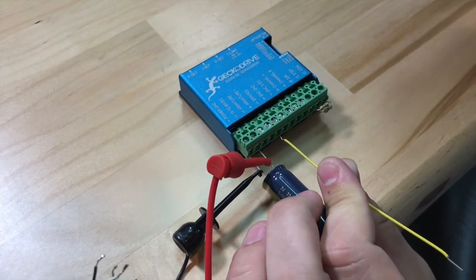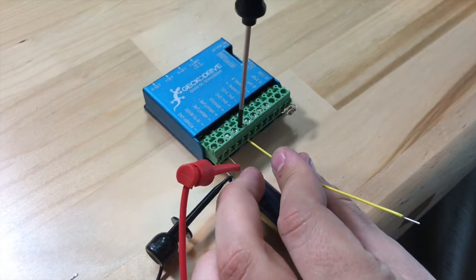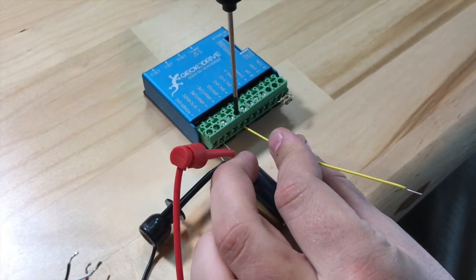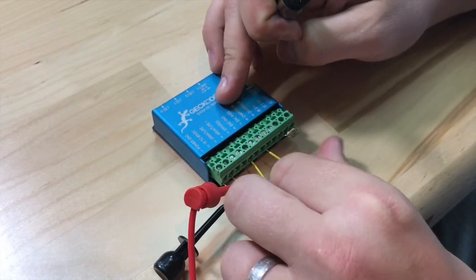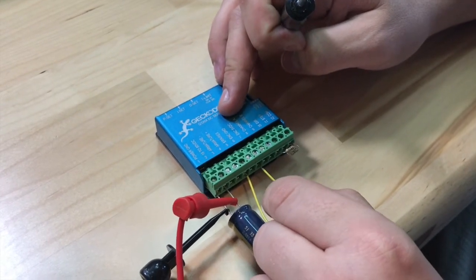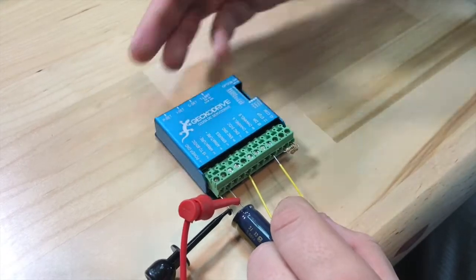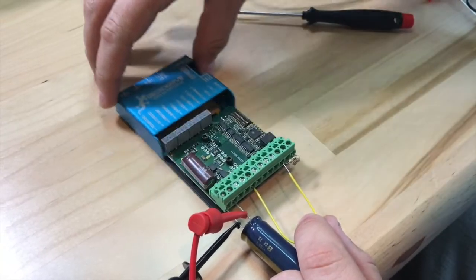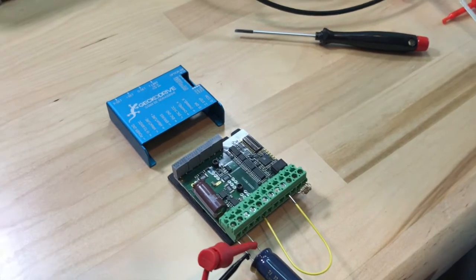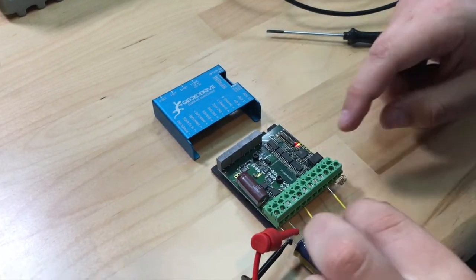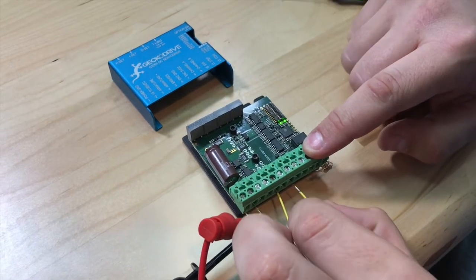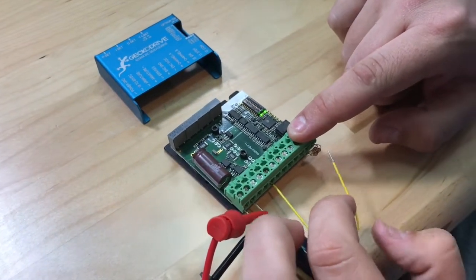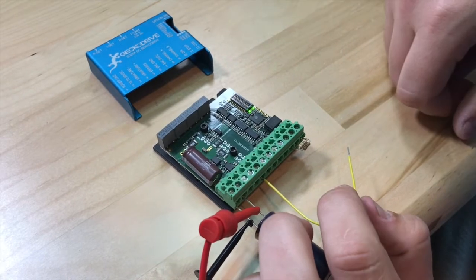So now that we have confirmed that the drive turns on and you get a red and green LED, we're gonna want to put a jumper wire between terminal 5 and terminal 7, which will be used in lieu of a momentary switch. Now we're going to power it on and make momentary contact for 3 to 5 seconds and you see it goes to the in position LED.